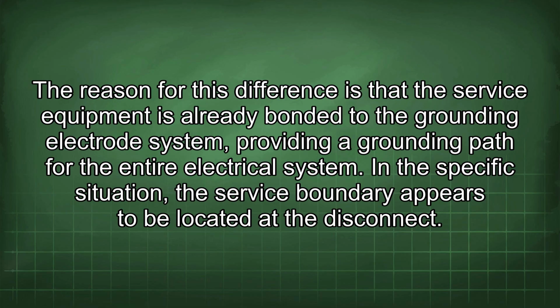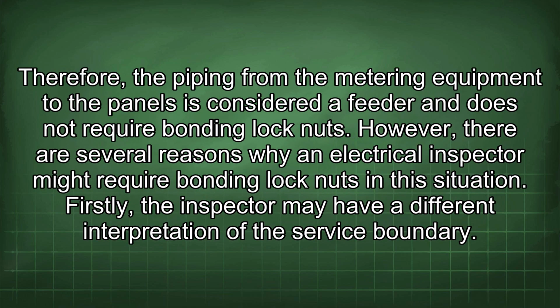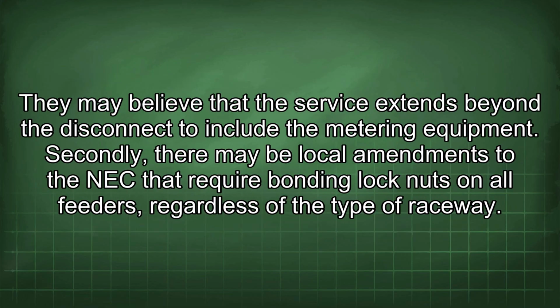In the specific situation, the service boundary appears to be located at the disconnect. Therefore, the piping from the metering equipment to the panels is considered a feeder and does not require bonding lock nuts. However, there are several reasons why an electrical inspector might require bonding lock nuts in this situation. Firstly, the inspector may have a different interpretation of the service boundary. They may believe that the service extends beyond the disconnect to include the metering equipment.